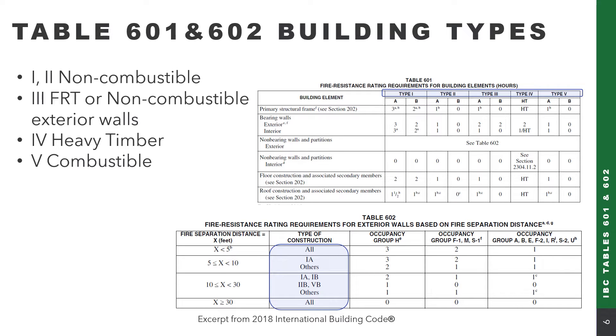Before we jump into Table 602, it's worth briefly mentioning building types, since that's going to be a critical part of the discussion. There are five different building types in the building code. Types 1 and 2 are considered non-combustible construction. Type 3 has non-combustible exterior walls or fire-retardant treated exterior walls with some additional fire rating requirements. Type 4 is heavy timber — large, thick wood members with additional fire endurance. Type 5 is combustible construction. These are critical factors in Table 601 and 602 of the IBC.